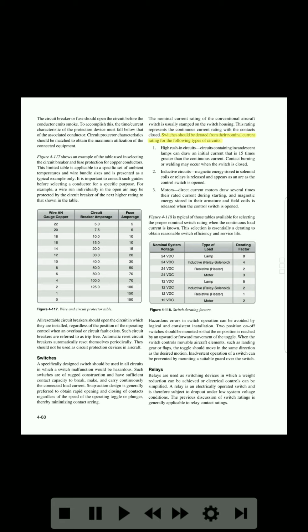Switches should be derated from their nominal current rating for the following types of circuits. 1. High rush-in circuits. Circuits containing incandescent lamps can draw an initial current that is 15 times greater than the continuous current. Contact burning or welding may occur when the switch is closed. 2. Inductive circuits. Magnetic energy stored in solenoid coils or relays is released and appears as an arc as the control switch is opened. 3. Motors. Direct current motors draw several times their rated current during starting, and magnetic energy stored in their armature and field coils is released when the control switch is opened.